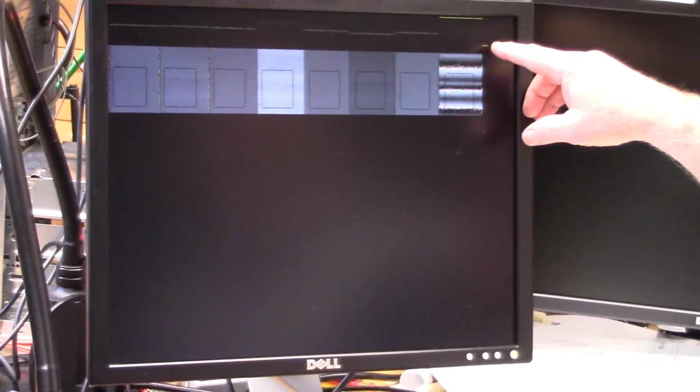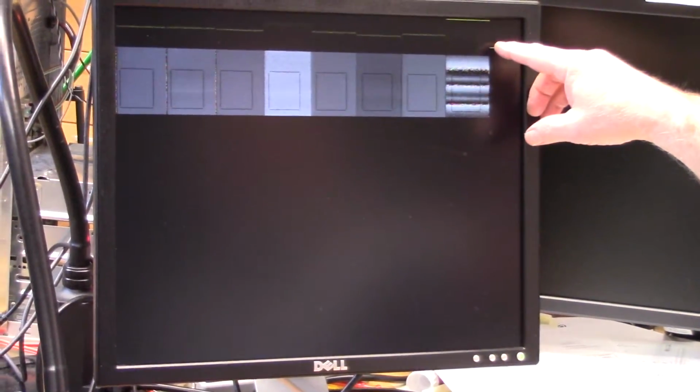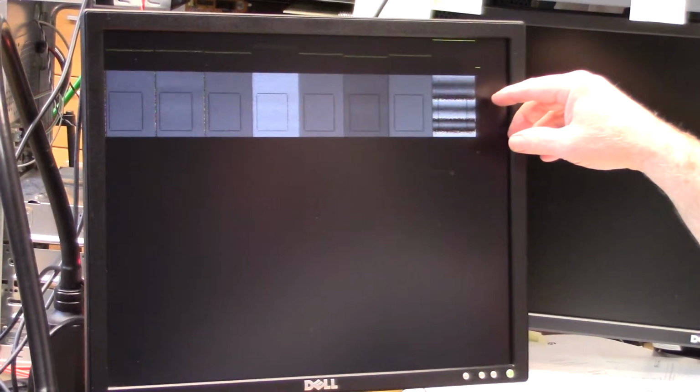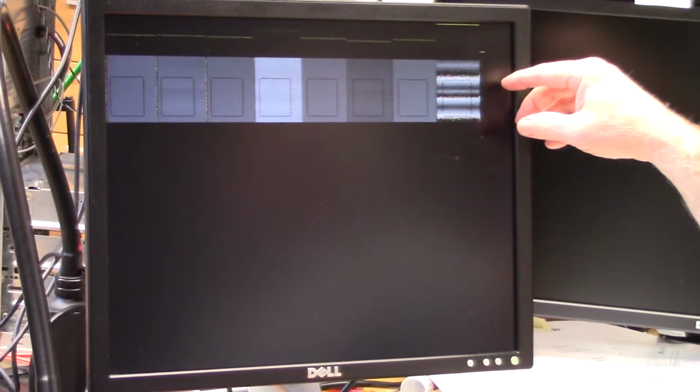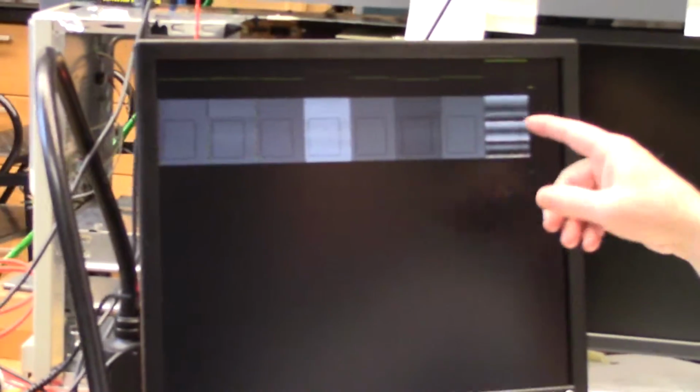And if we look at what we've got here on the screen, we don't have our nice flat field anymore at all. On channel 8 especially, we've got this signal going up and down and up and down at 1 hertz, because it's the 1 hertz signal that we're injecting and it's not being rejected. That is, the common mode rejection ratio on channel 8 is terrible.